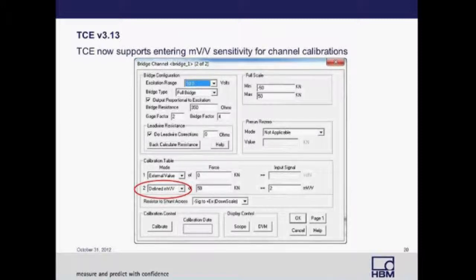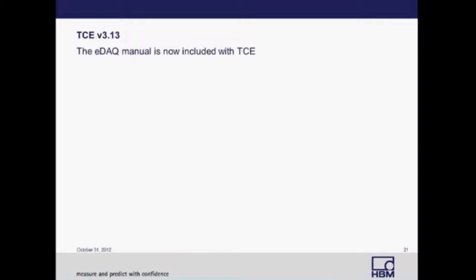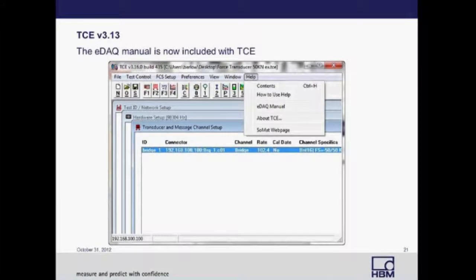Also in TCE version 3.13, TCE now supports entering millivolt-per-volt sensitivities for channel calibrations. Prior to this, if you had a transducer with a millivolt-per-volt sensitivity, you would have to calculate its sensitivity based on its excitation. Now you can define it directly in the pull-down menu on the calibration table. Another update in 3.13 was that the eDAQ manual is now included in TCE — go to the toolbar and select Help, then select the eDAQ manual.